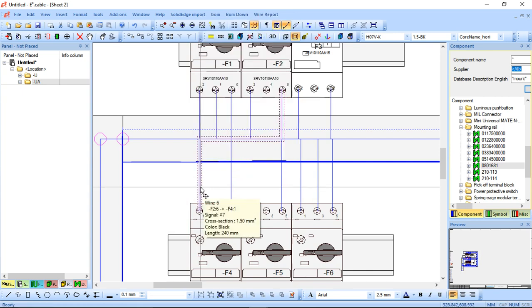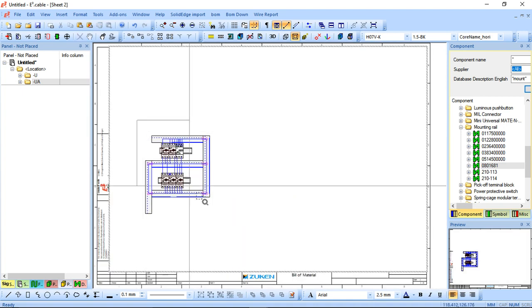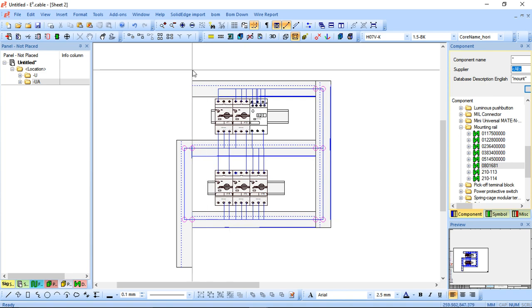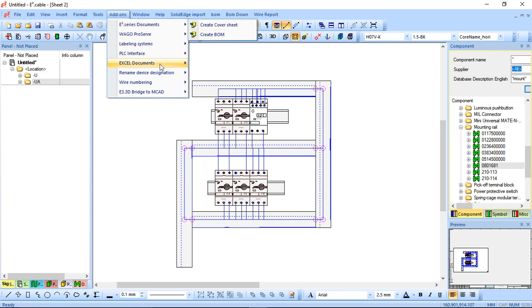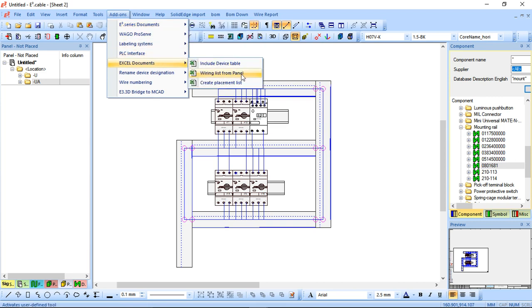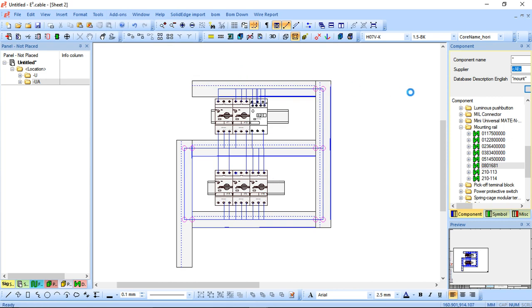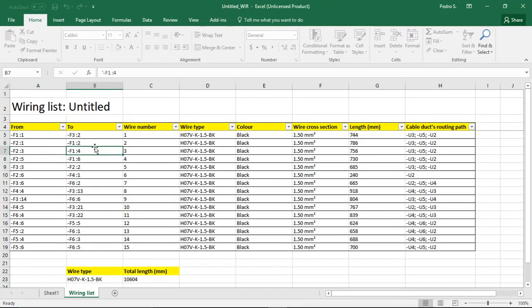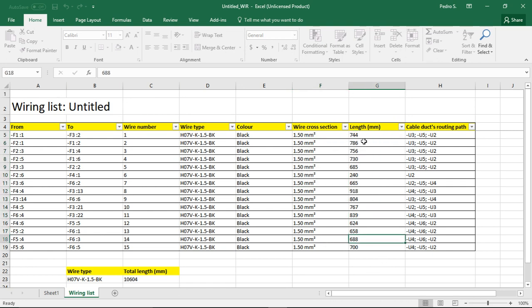So I can right click and hover over it and it's going to tell me that the length is 240 millimeters. So what that's actually doing is once I've got my panel set up, it's actually going to give me the cut lengths exactly to the requirement based on what you've done. You can actually create — there's a tool here. If I go to E3, there's an Excel document and there's a wiring list from panel. I'll just bring this one up quickly and it's actually going to create a table for me for every single one. So you can see it's giving me a from, a wiring number, a wiring type, a color, a cross section, and it tells me every single length of every single cable to the millimeter.